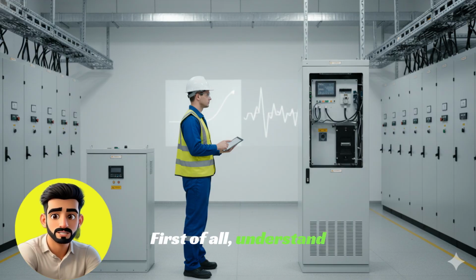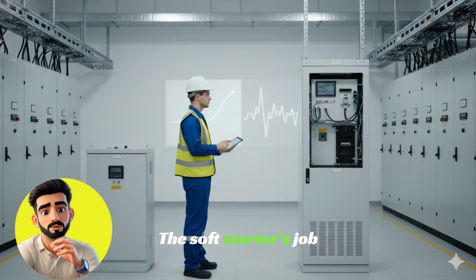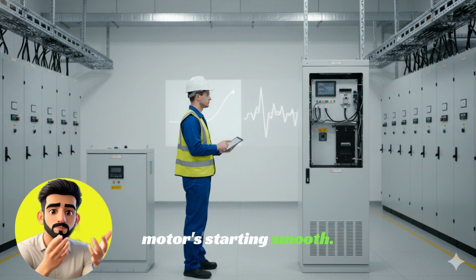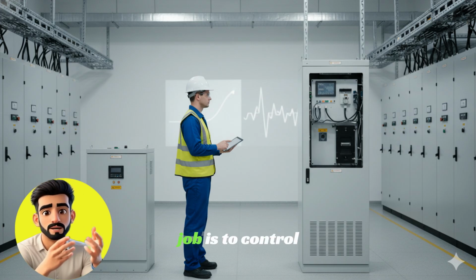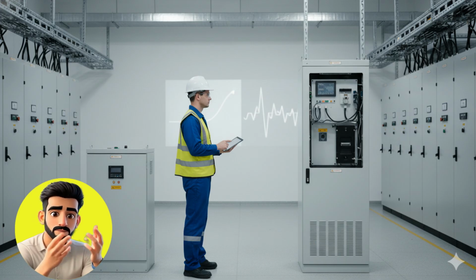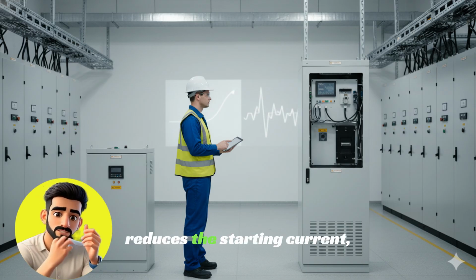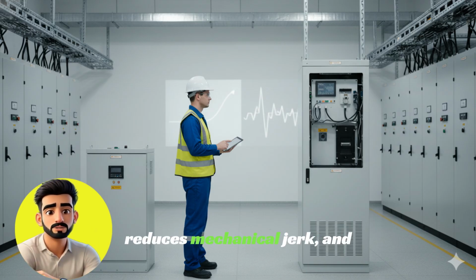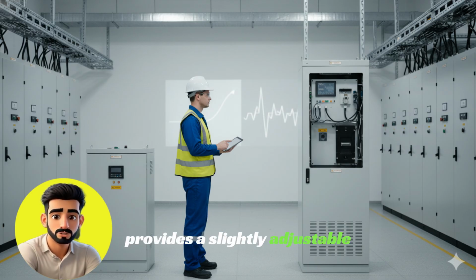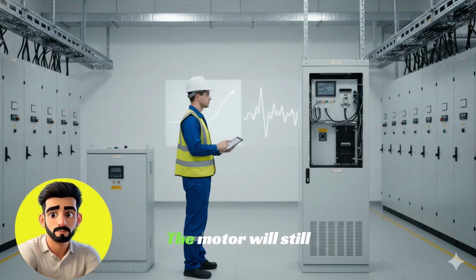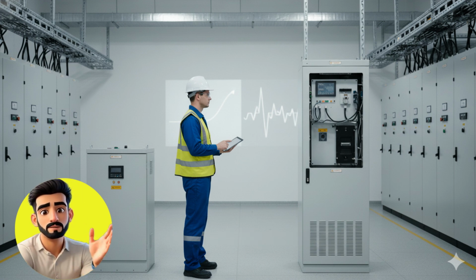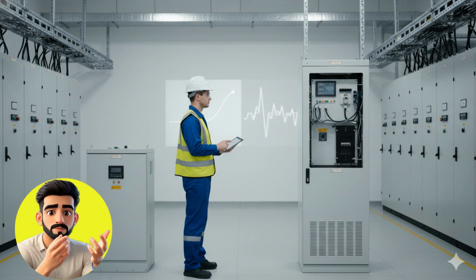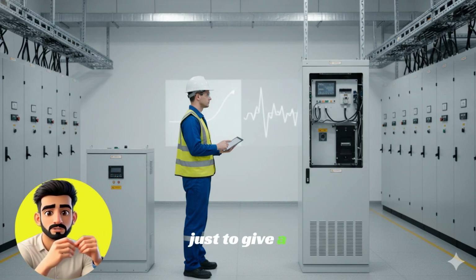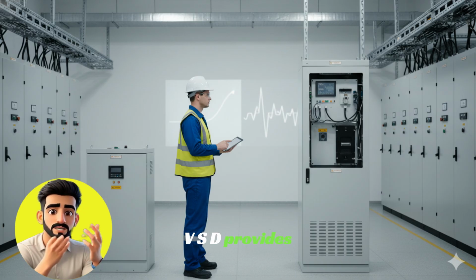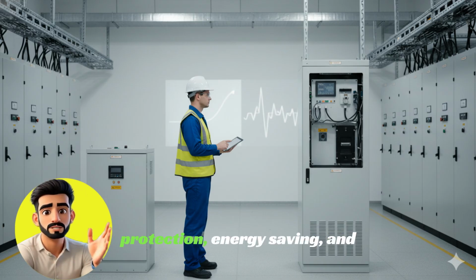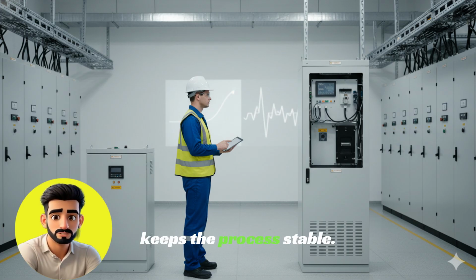First of all, understand it in a simple line. The soft starter's job is to make the motor's starting smooth, and VSD's job is to control the motor's entire life. The soft starter mainly reduces the starting current, reduces mechanical jerk, and provides a slightly adjustable starting torque. The motor will still run at full speed, just the starting is smooth. The role of VSD is not just to give a soft start. VSD provides speed control, torque control, protection, energy saving, and keeps the process stable.